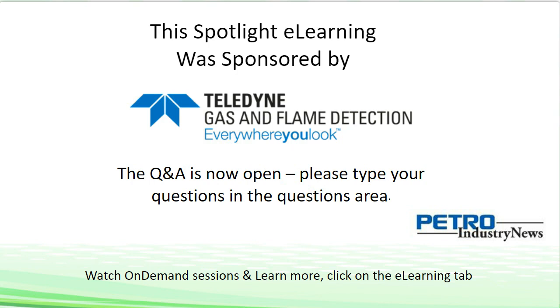If, on the other hand, it's a very simple system, the hazards are very low, there are lots of other devices that could also indicate that there's a problem, then perhaps a SIL 1 system is appropriate at significantly less cost. Safety is really important, but we don't want to overburden. Everything needs to be proportionate. And the appropriate SIL level will be determined by earlier steps in the safety management processes.